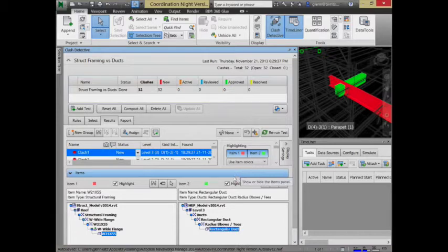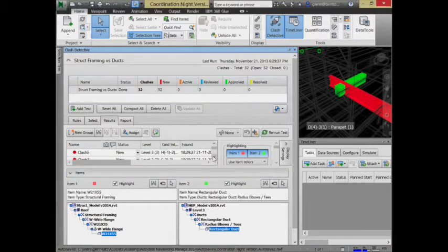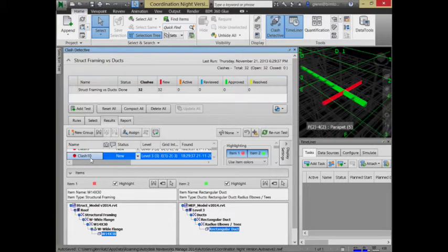Okay, let me go popping on down the list a little further. Here's another clash. Again, it looks like I have some big old rectangular duct, and it is conflicting with this beam coming across. It's this big, long run of duct. That's going to probably be a pretty good one to fix. So what I'll do is I'll say switchback.